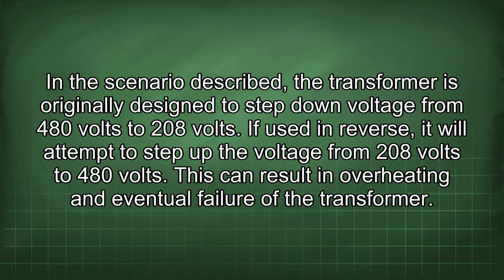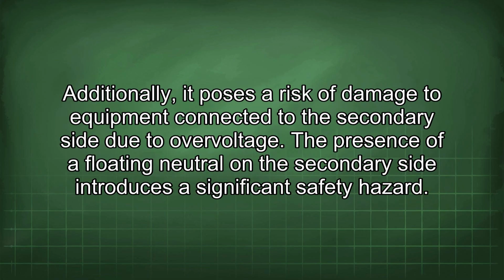In the scenario described, the transformer is originally designed to step down voltage from 480 volts to 208 volts. If used in reverse, it will attempt to step up the voltage from 208 volts to 480 volts. This can result in overheating and eventual failure of the transformer. Additionally, it poses a risk of damage to equipment connected to the secondary side due to overvoltage.